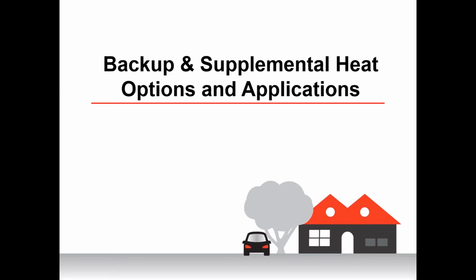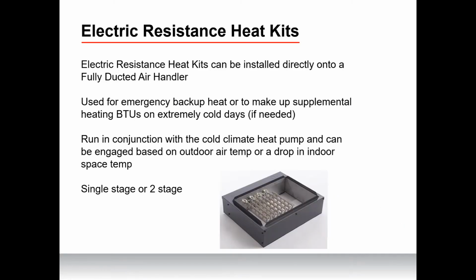Lastly, if there's already a heating source in place, like a boiler, and an air source heat pump is being installed primarily as a cooling solution, it makes sense to utilize both heating systems at optimum times for energy savings and comfort benefits. So if you already have a good heating source in place and you're installing an air source heat pump primarily for cooling, let's utilize both here and get the most efficient and comfortable option. Let's look at electric backup heating options first. The most common that we're going to integrate into our systems is electric resistance heat kits.